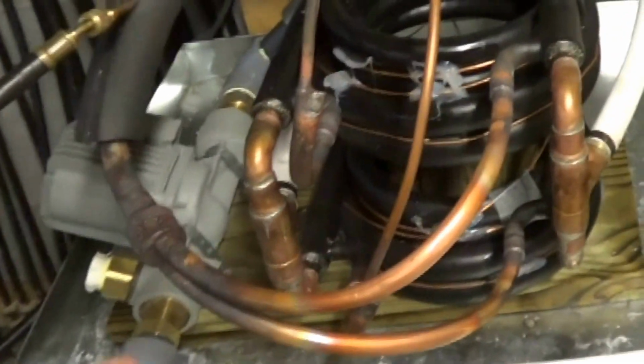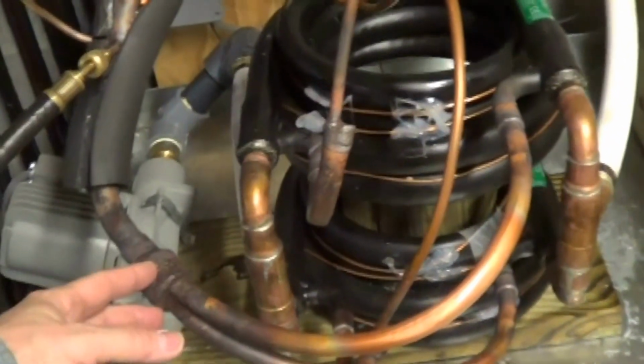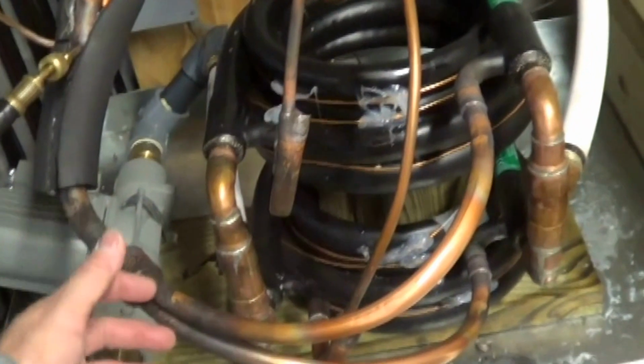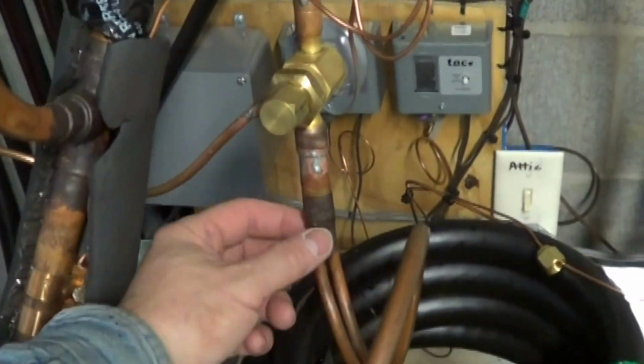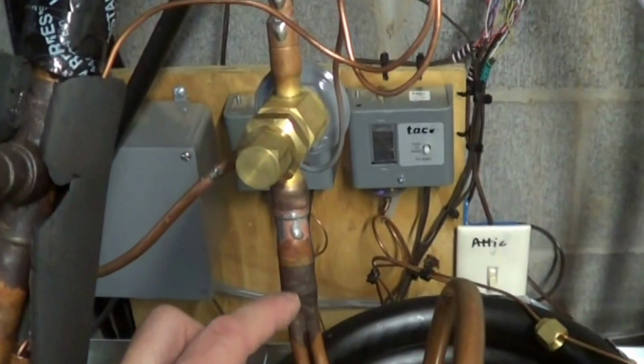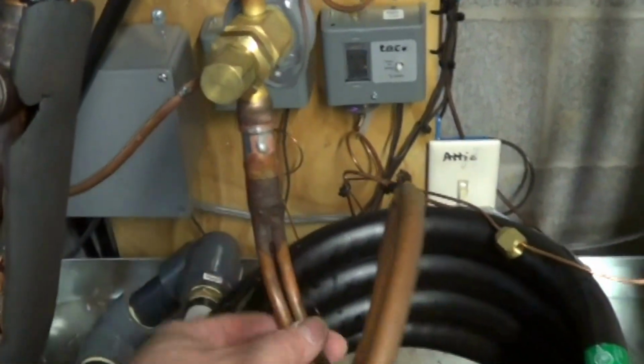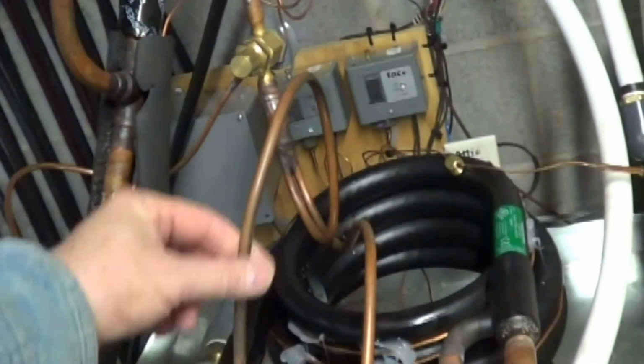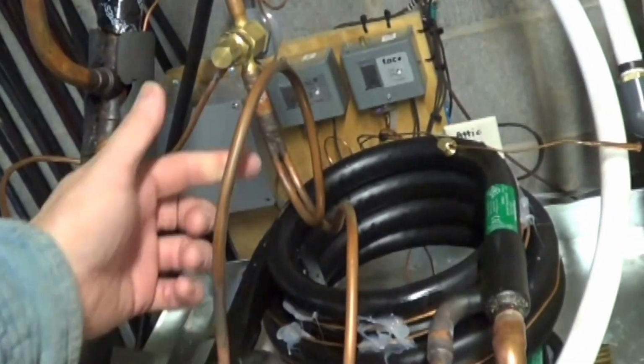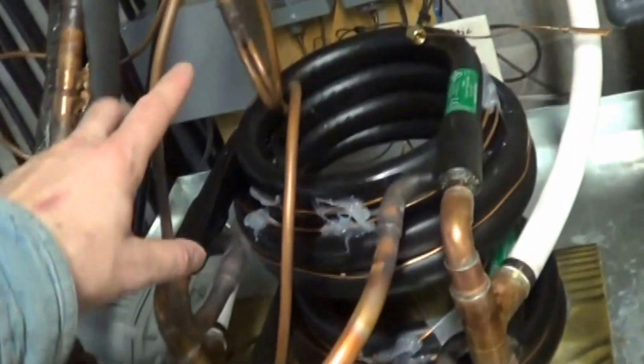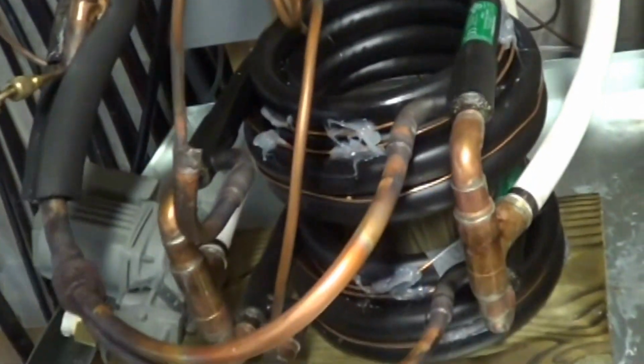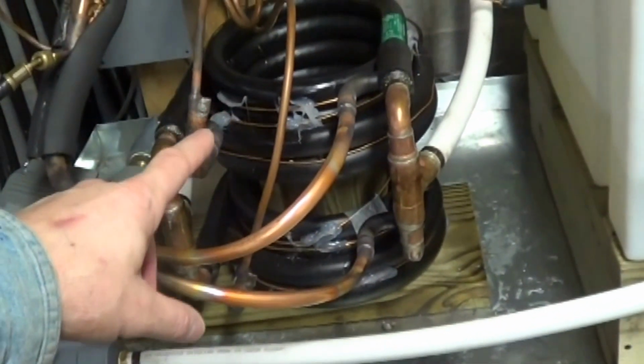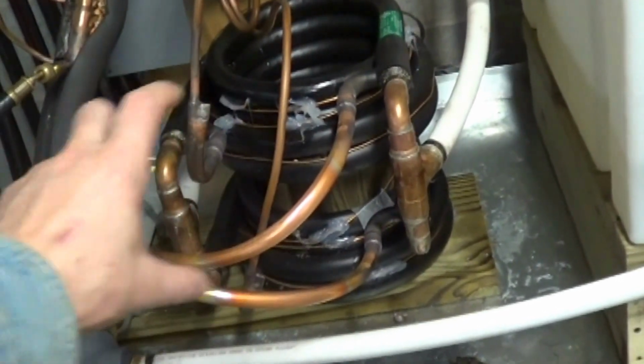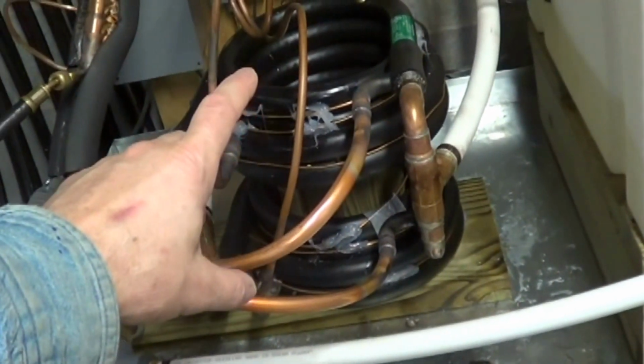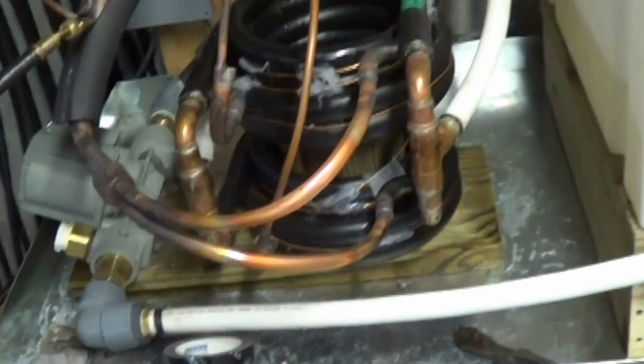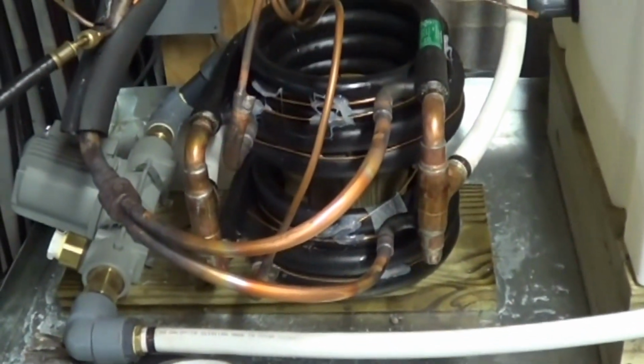Finish the repiping, so you can see the outlet on the heat cycle, inlet on the cooling cycle, and made sure that the pipes are exact same height there. Chart shows 5/16 for 2.5 ton, 2 foot long. It's important these are the same length. So basically now we got 2 3.5 ton coils in parallel, so it's a 7-ton coil. Should work much better now.